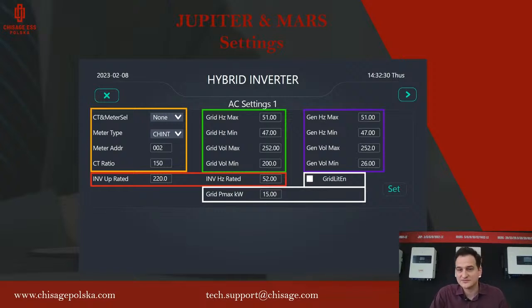So now it's 15 kilowatt maximum power, but we also have the grid limitation enable. If it's not checked, this grid limitation is not working. We have to check this box, then this grid limitation is on, and the inverter will limit the power taken from the grid to this. So now for 15 kilowatts.